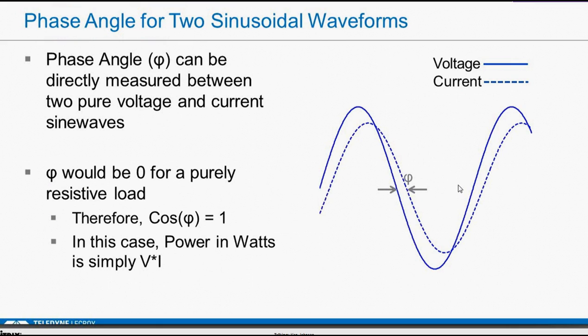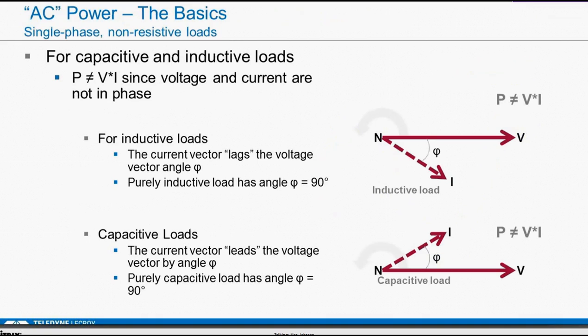All right, so if we have a phase angle, now we have these two waveforms. If you had your current and your voltage waveform, and they were purely sinusoidal, it'd be really simple. You could just measure the phase angle by the delay at the zero crossing point, convert that into radians or degrees, and then you could measure the power factor from that by taking the cosine of the phase angle.